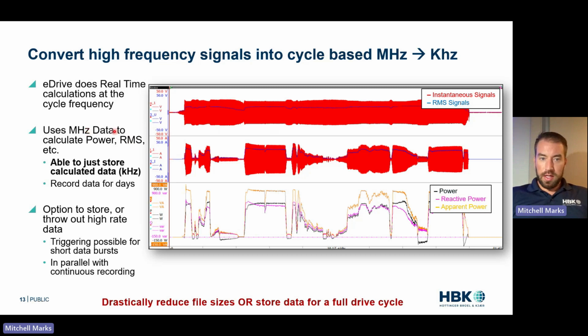You're able to turn that megahertz data into calculated power RMS results that you can store. So you're able to just calculate at, let's say, kilohertz rate. And you can do this for days because the data rate is so low. And we do have people doing durability tests who are running tests like this for like 80 days, 2,000 hours. And you might say, well, what if I want to store that data? There's triggering options. But what you end up with is that high frequency sine wave of voltage and current that you see in red, and then you have that time averaged RMS that you're just storing at the kilohertz rate.